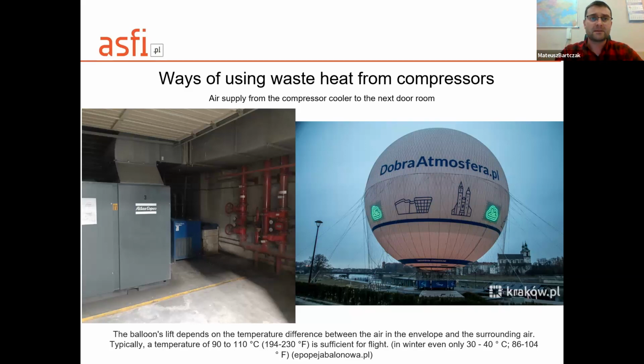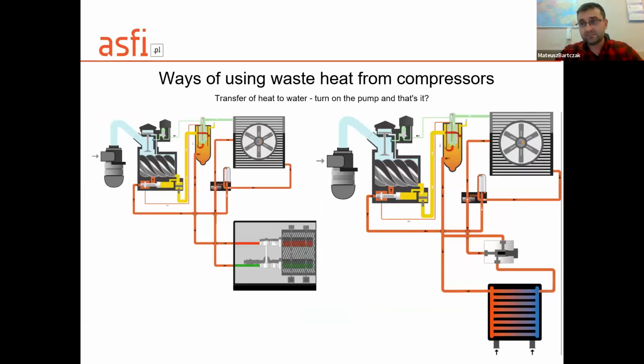Why do I talk about it? Because think how this air can behave when it enters the hall. This air after the cooler is between 60 and 70 degrees. It will fly up to the roof and it will stay there. I talk about it because it's not an effective way to use heat from air compressors, but of course it's better than disposing of it to the atmosphere. The second, and in my opinion the only correct method of recovering heat from an oil-injected compressor, is to transfer the heat to water and transfer it to the place, to the process of heat demand, and use it there.